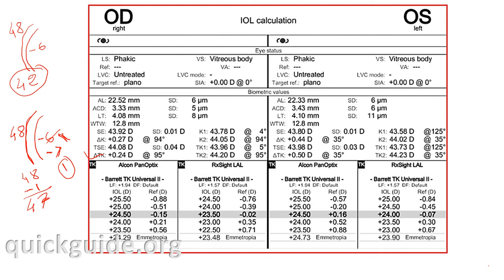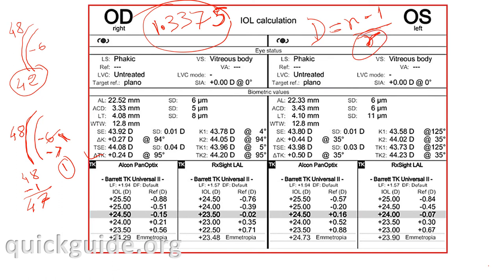That is why they never had to change the keratometry index from IOL Master 500 to IOL Master 700. The IOL Master 700 still uses a keratometry index of 1.3375. For those who may not know what a K-index is — I have explained this on my site — it converts the keratometer measurement in millimeters, the radius of curvature, into diopters through the equation (n − 1) / r, where n is the keratometry index.